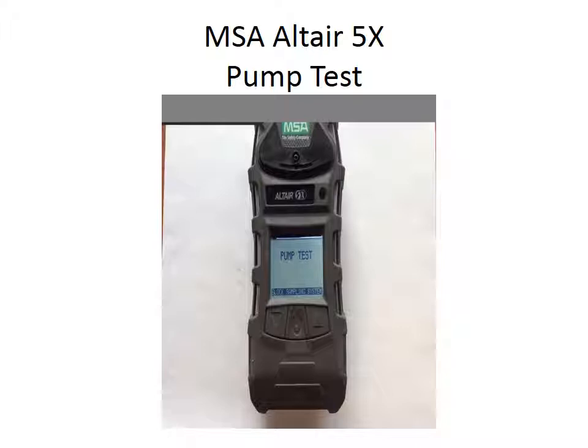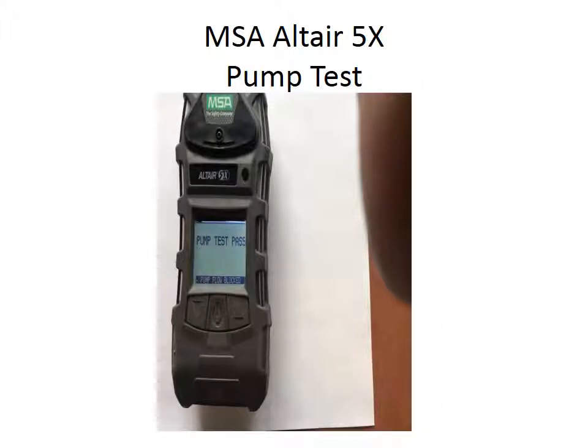And ideally, when we talk later about the probe, in a lot of situations we want to be using that probe, and this is where you want to do the pump test with that probe attached to make sure there's not a leak anywhere in that system. So once you block that, the meter will tell you whether or not it passed that system, and then it goes on to the next part of the process. So there you see in this next screen, it says the pump flow was blocked and the pump test passed, and it's going to continue on in its setup of the meter.